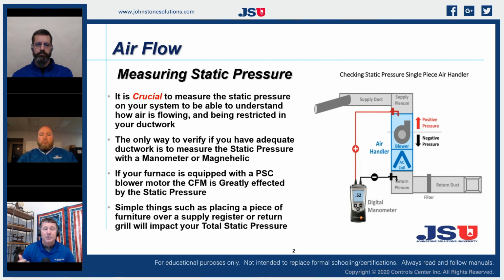So if someone gives me some data, maybe if I'm doing a tech support call and we're working on an air handler and I ask them to check the static pressure, and they check it at the return right in front of the air handler, and at the supply right past the blower, which is where they would typically check that, but they have a filter in that air handler, it does not include the pressure drop across that filter.